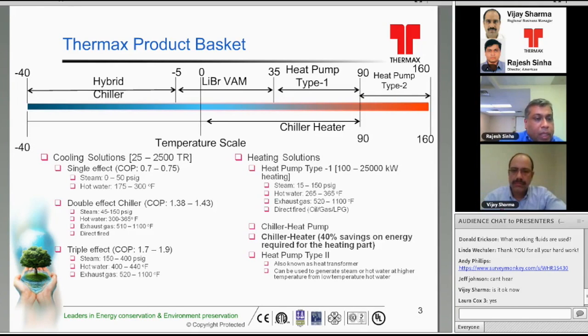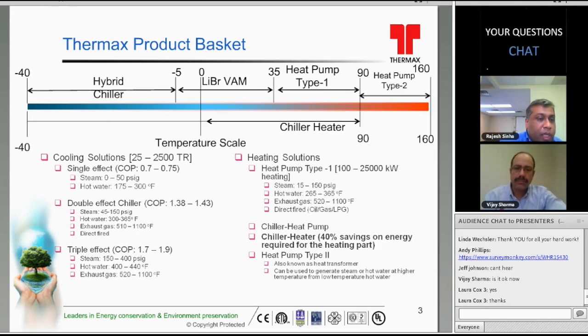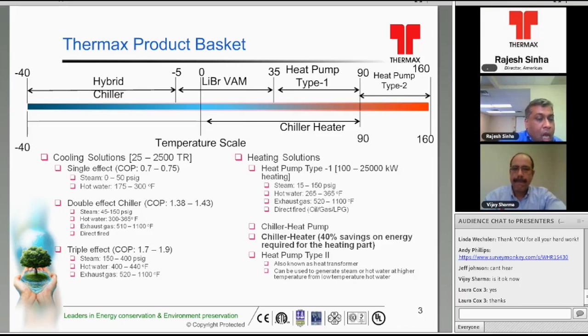So on the cooling solution, I would like to update everybody that these absorbers are definitely available below 100 tons of capacity. We, in fact, begin at 25 tons of capacity with the single effect absorbers, which currently have an efficiency of 0.7 to 0.75. And the single effect absorbers can be run on steam or hot water. The steam could be between 0 to 50 pounds, or hot water could be between 175 to 300 degrees.